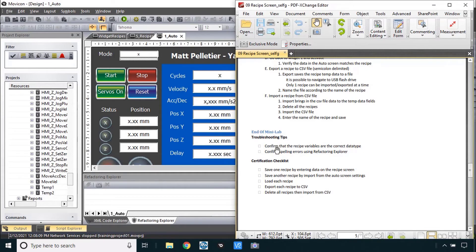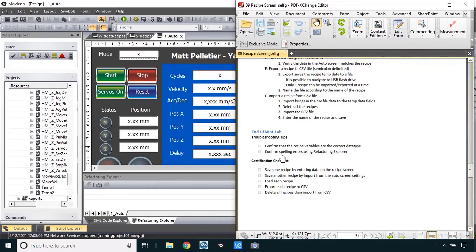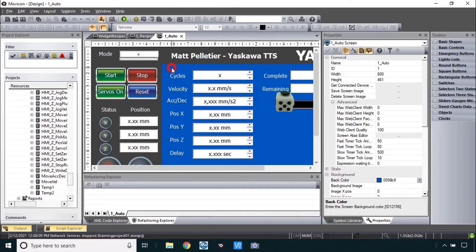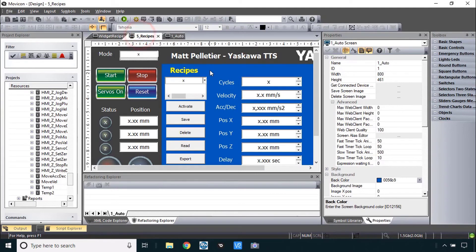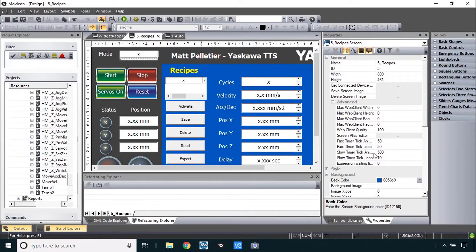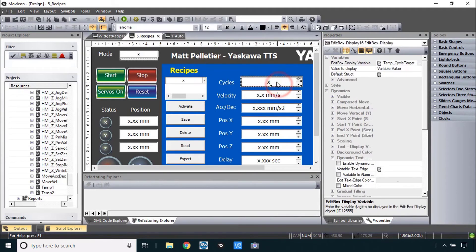Main troubleshooting tips on this one is just the data type has got to be correct for all of those variables. And I've also seen spelling errors and you can try to check those with the refactoring explorer. Remember just click on the screen. Click on my recipe screen see if I have any issues. Click on an area that's blank and those should pop up.